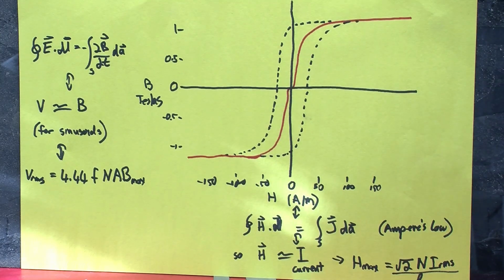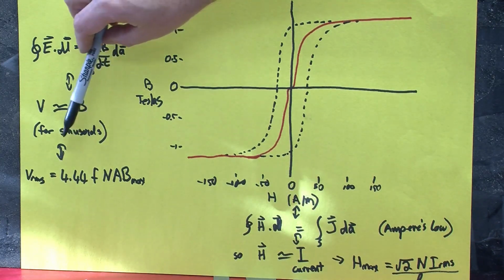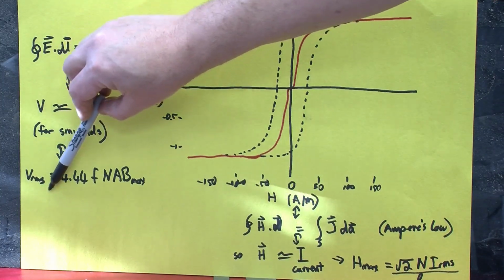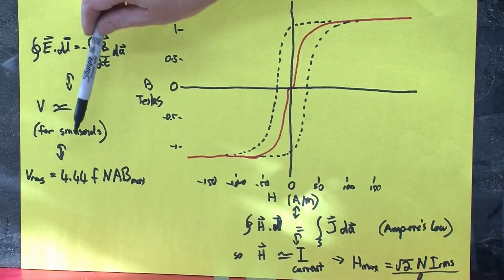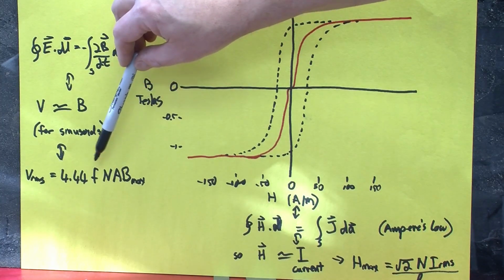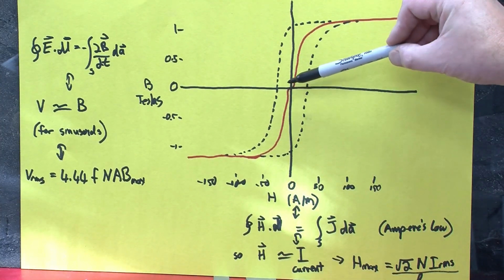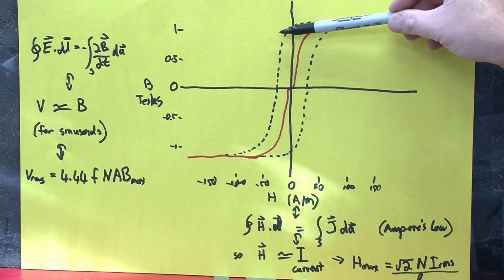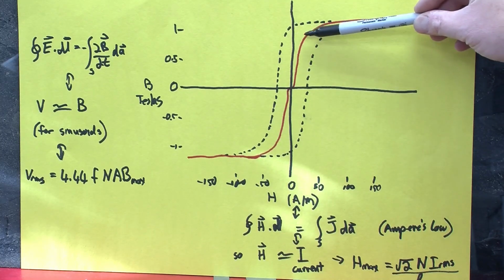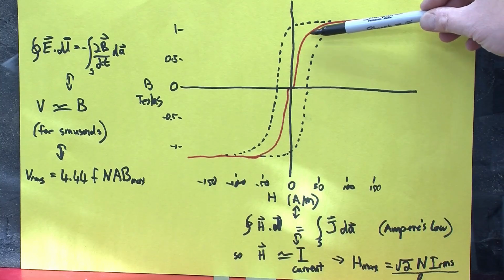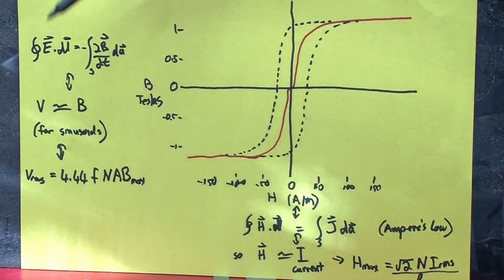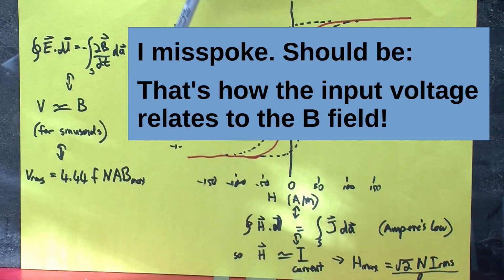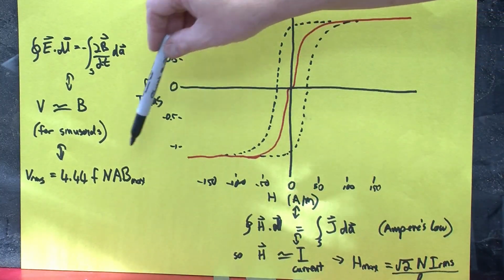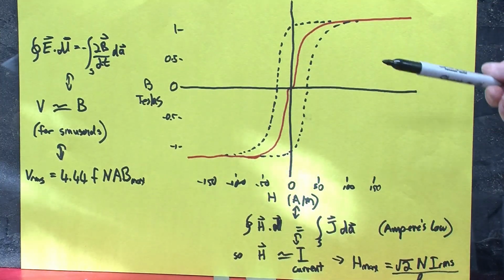When you reduce it all, you get a couple of simple equations describing the operation. The output voltage of a transformer in RMS, the type normally seen on voltmeters, is a little over 4 times the frequency times the number of turns times the area of the core times the peak of the B field. We talk about the peak of the B field because transformers are typically designed so the peak doesn't go much above this point, avoiding those horrible current spikes. So that governs the output voltage — essentially how big the B field is, the area of the core, and the number of turns in the coil.